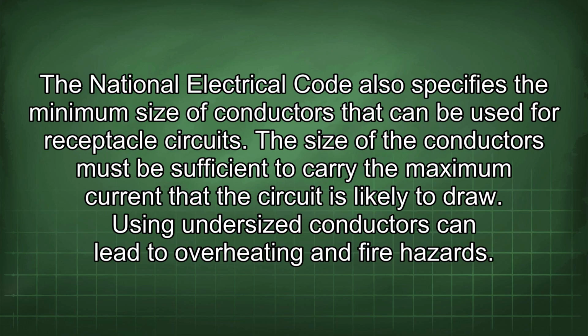The National Electrical Code also specifies the minimum size of conductors that can be used for receptacle circuits. The size of the conductors must be sufficient to carry the maximum current that the circuit is likely to draw. Using undersized conductors can lead to overheating and fire hazards.